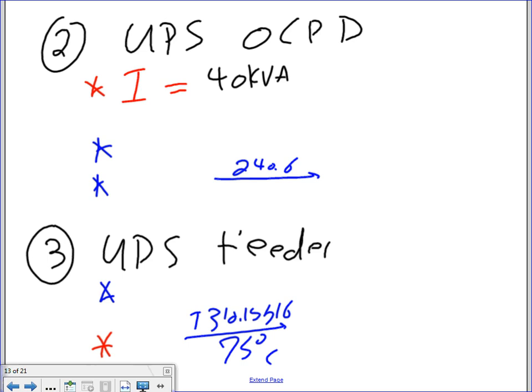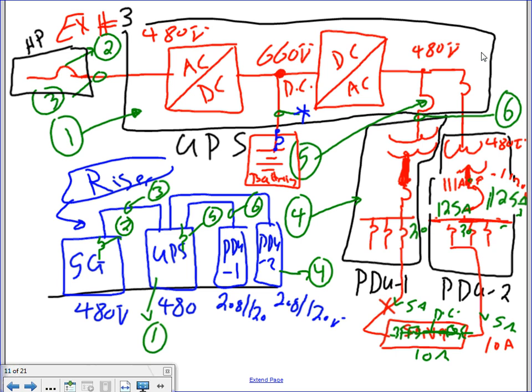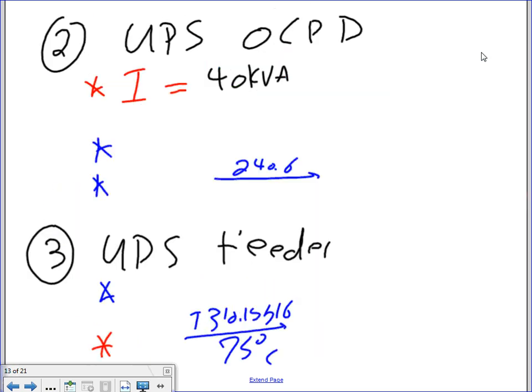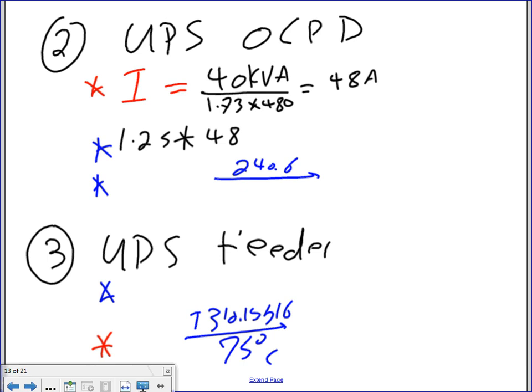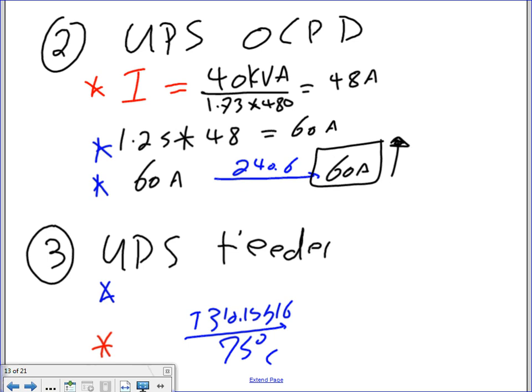Now you size the overcurrent device for the UPS. Remember, we came up with the size of the UPS. Now I want to go to number 2, the overcurrent device. I want to size that. Okay, Adam, we need amps, so you divide this by 1.73 times 480. It's a 480 system, so that will get you 48 amps. Then you multiply by 1.25 for the continuous load, and that will get me 60 amps. You take your 60 amps to 240.6, and that will get you 60 amps. If it's not standard, you go up, and that's my 60 amp circuit breaker. So you take a 60 amp circuit breaker there, for the feeders to the UPS. Done.